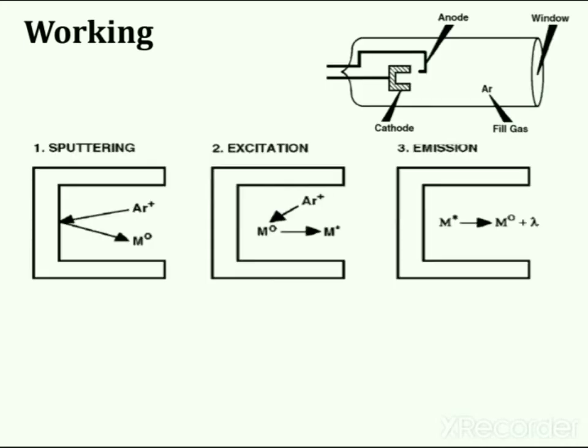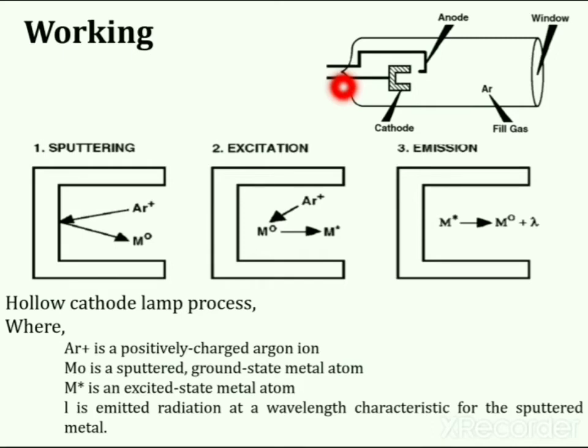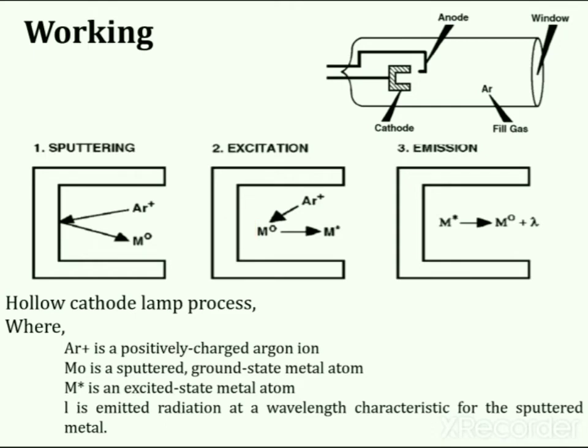When an electrical potential is applied between the anode and cathode, some of the fill gas atoms are ionized. The positively charged fill gas ions accelerate through the electrical field, collide with the negatively charged cathode, and dislodge individual metal atoms in a process called sputtering. Sputtered metal atoms are then excited to an emission state through kinetic energy transfer by impact with fill gas ions, and the excited atoms generate an emission spectrum. In this process, Ar⁺ is the positively charged argon ion, M⁰ is the sputtered ground state metal atom, M* is the excited state metal atom, and L is emitted radiation at a wavelength characteristic to the sputtered metal.